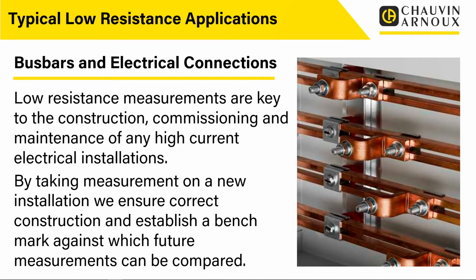And it's very typical that if we have got bad connections, that's going to be a hotspot. If that's a bad connection, it's carrying that current through a smaller cross-sectional area. We can end up creating hotspots. That'll be a failure point. It'll be something where it gets hotter, which could cause thermal cycling, which could mean your nuts, your connections, are more likely to come undone and all sorts of things.